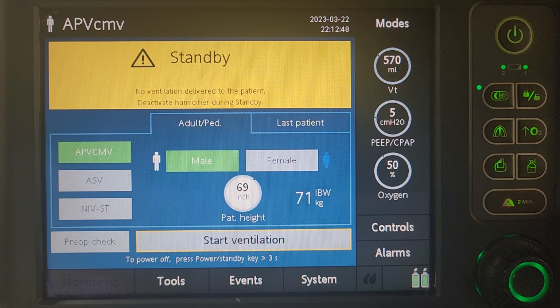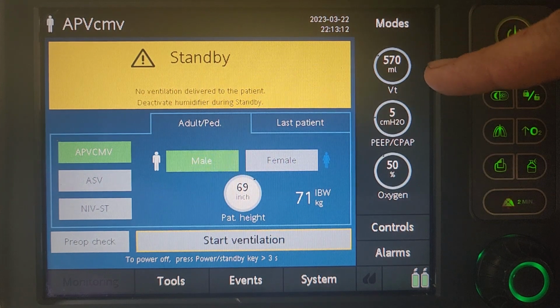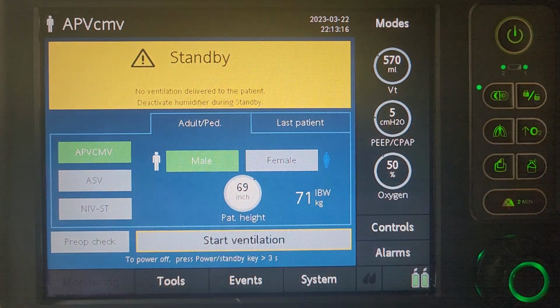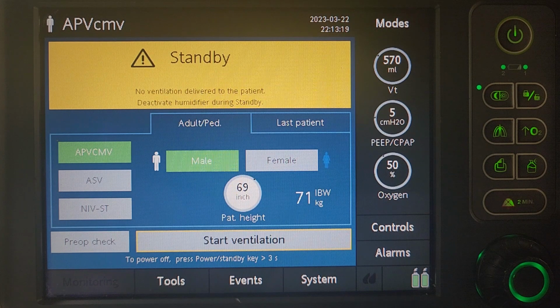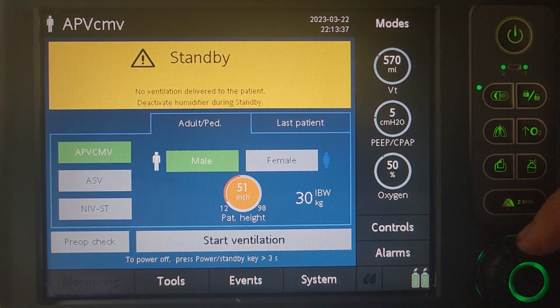volume controlled adaptive mode. The preferred mode for ventilation is going to be a pressure mode for children. So the difference between the two modes, when you use this volume adaptive mode, the ventilator is going to attempt to adjust itself internally based on its protocol. So when you use a volume mode and you're showing your volume here, you want to set the volume, you want to make sure that it's delivering the tidal volume close to where you have it set, but you want to monitor the pressures. When we use a pressure mode, we want to monitor the volume. So it's exactly the opposite for each one. So let's go down to our 5 kilo patient that we were talking about earlier.